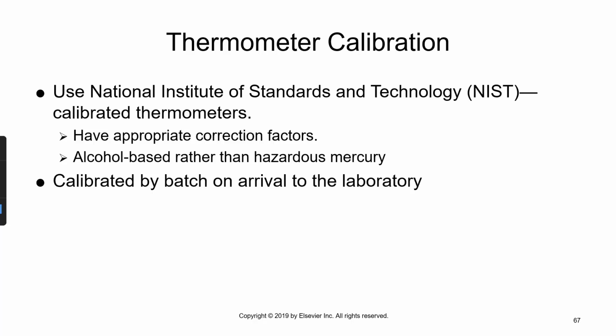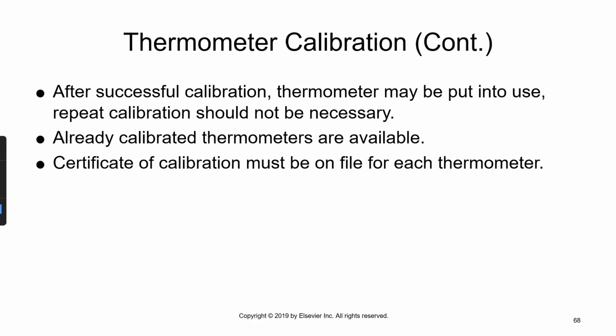We use National Institute of Standards and Technology calibrated thermometers, and they're calibrated by batch on arrival to the laboratory. After successful calibration, the thermometer may be put to use. Repeat calibration should not be necessary.